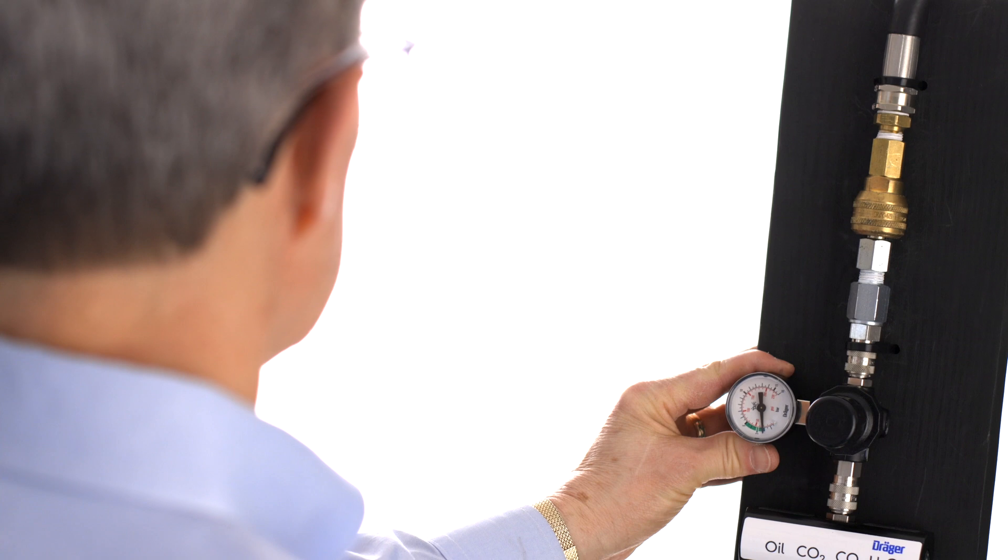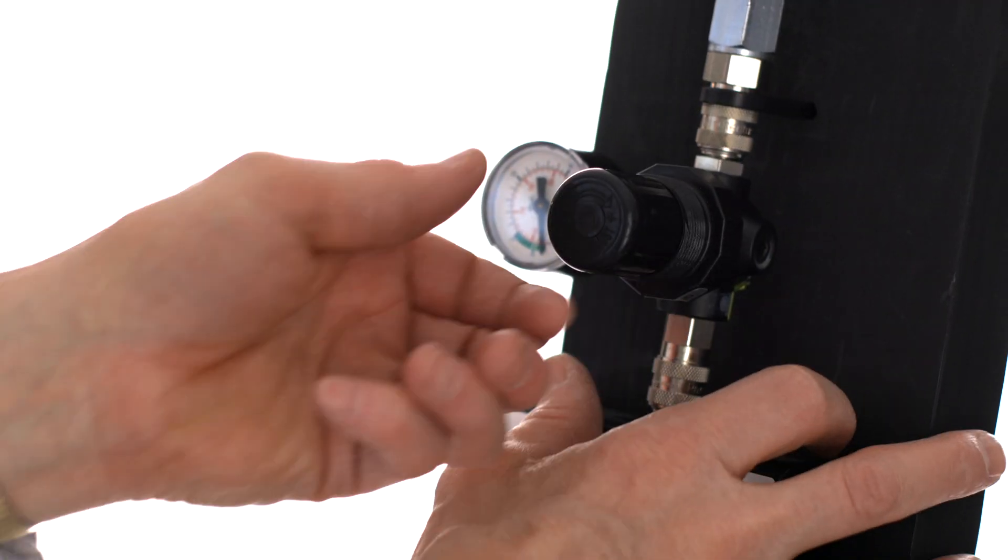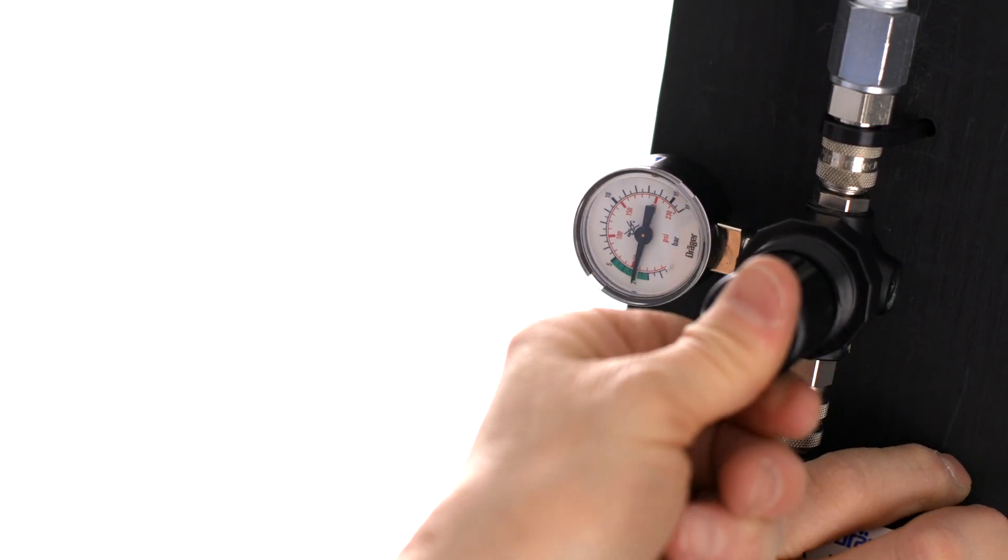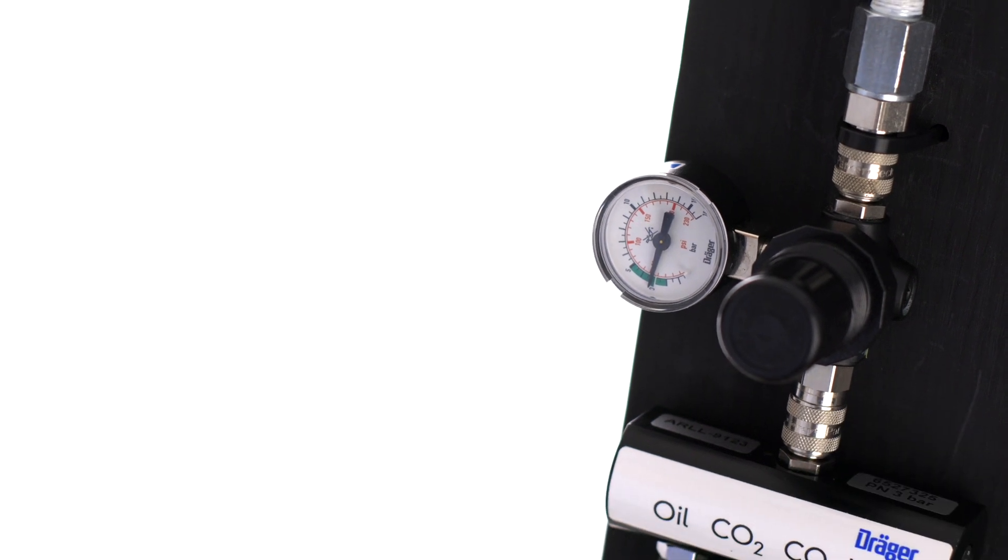Check the reading on the pressure gauge. If it's not reading 3 bar, pull out the black hand wheel and turn it to set the pressure to 3 bar. Since the pressure reducer is not self-compensating, the gauge must be checked for each application to ensure the outlet pressure to the measuring device is set properly.